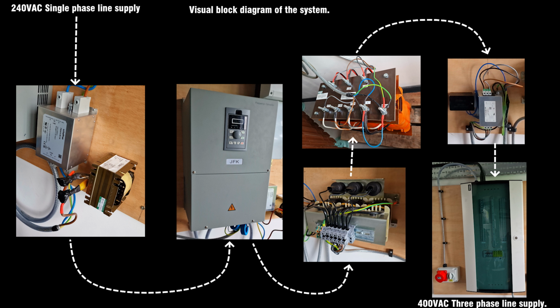If you wish to have a neutral or a proper ground reference voltage for electronics, like used in CNC machines, etc., you will require a delta to Y isolation transformer. It must be an isolating type transformer. That is very important. The modifications mentioned to the VFD are quite basic, but are important. VFDs of this size, mine being 22 kilowatts, usually are all 3-phase inputs. You'll have to ask the manufacturer if you can run them on single-phase supplies.